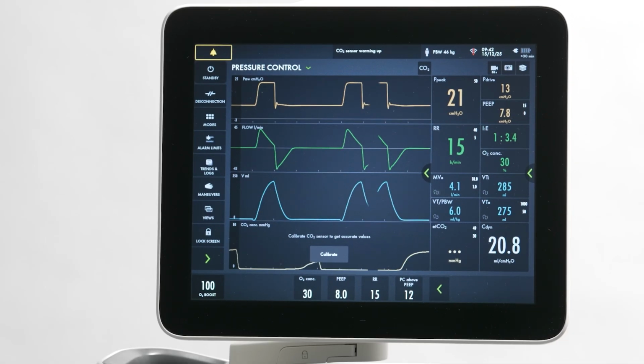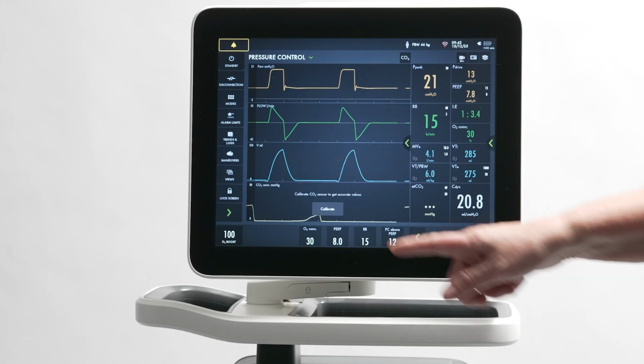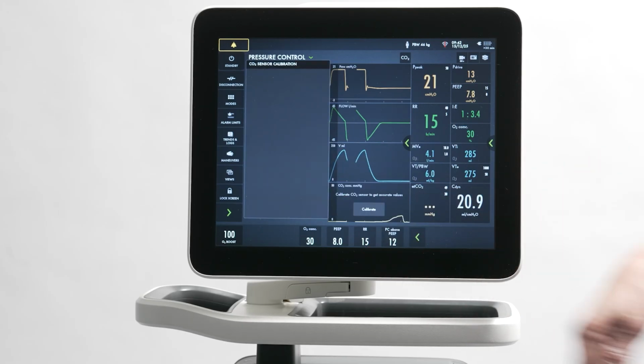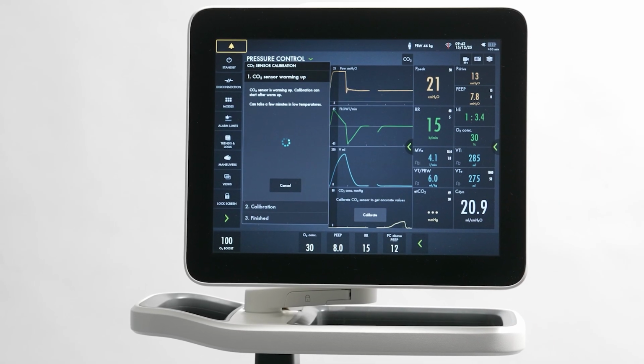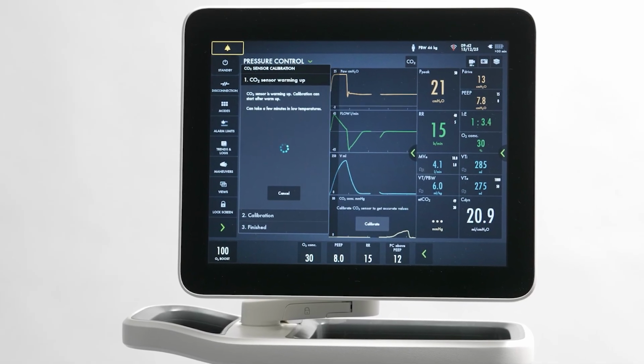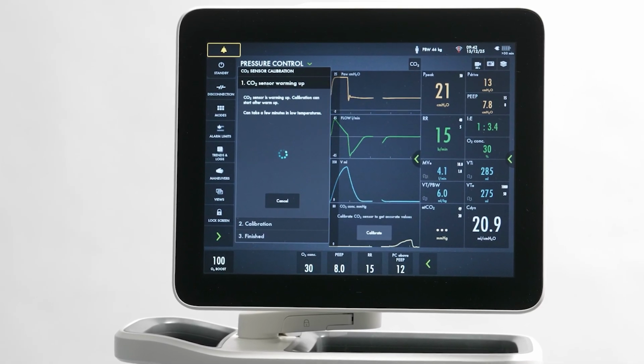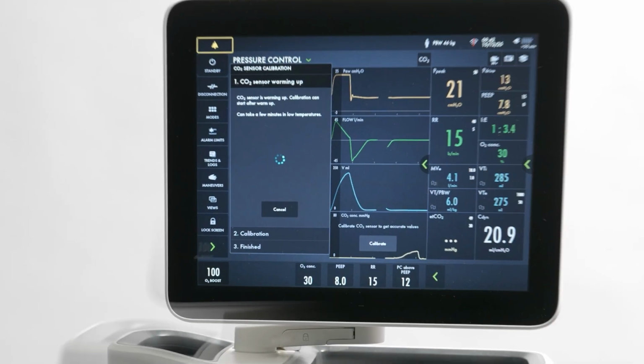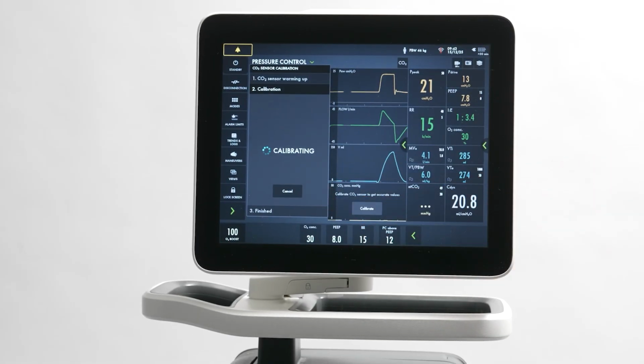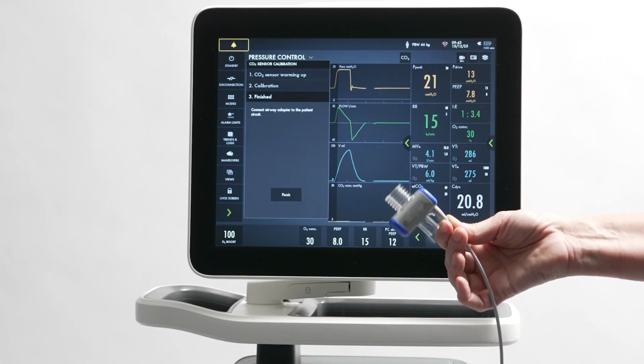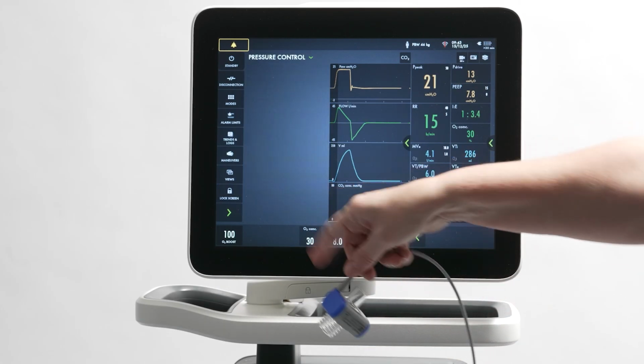I will now show how to calibrate the sensor. Each step of the calibration is displayed before beginning the calibration procedure. The sensor needs to be warmed. This is done automatically. Note this can take a few minutes. Final step is to connect the CO2 adapter to the patient circuit.